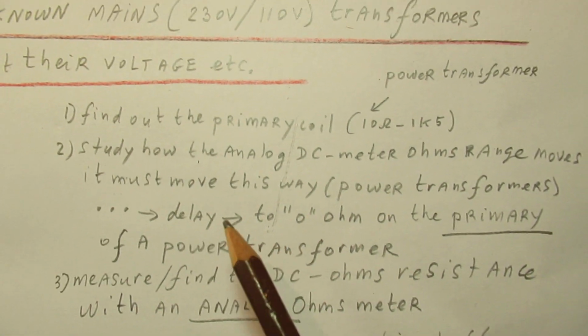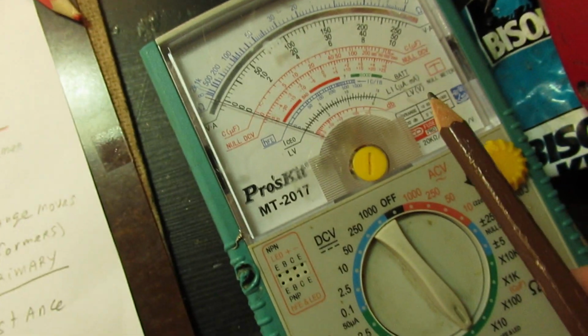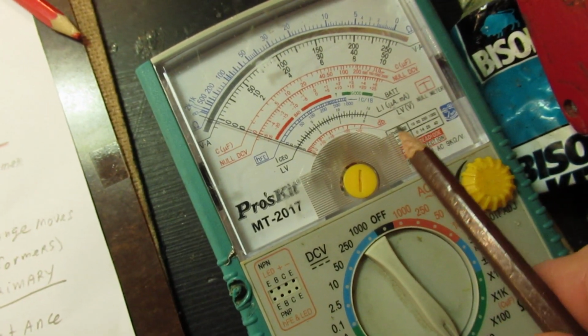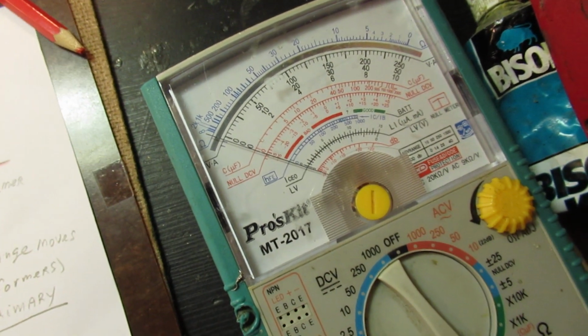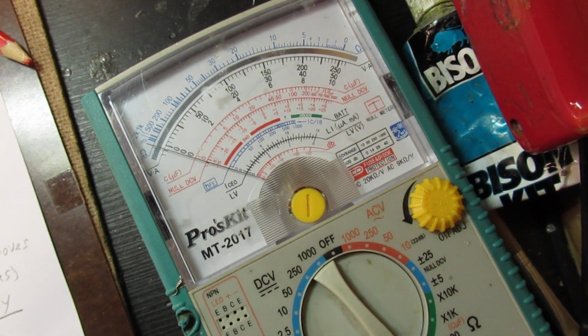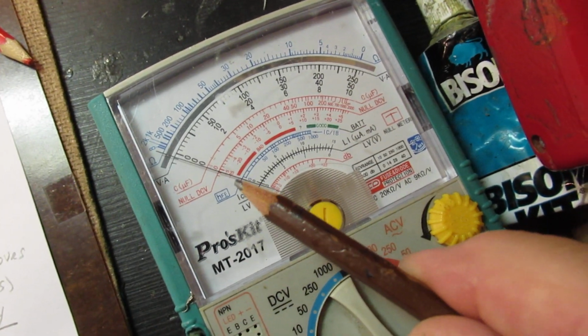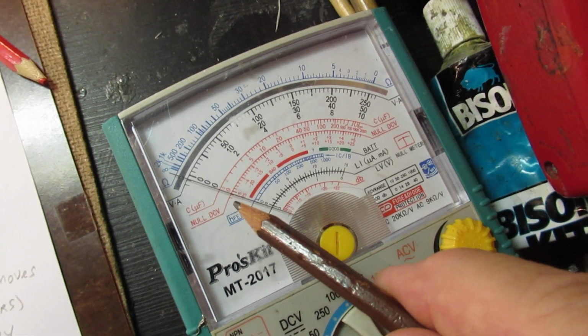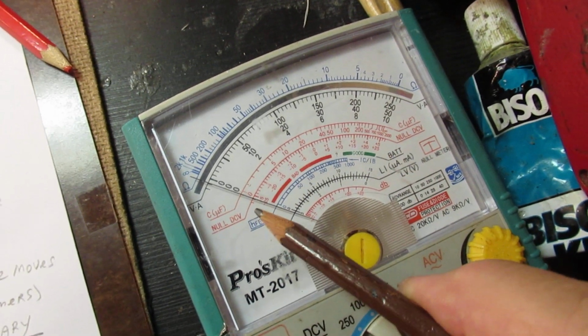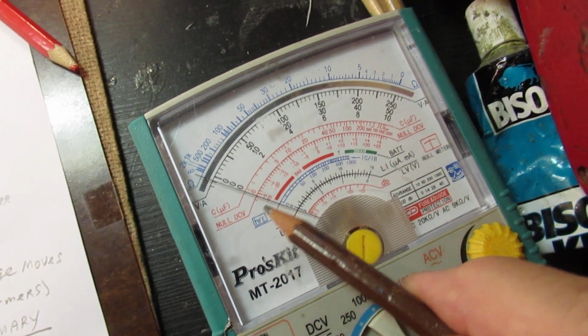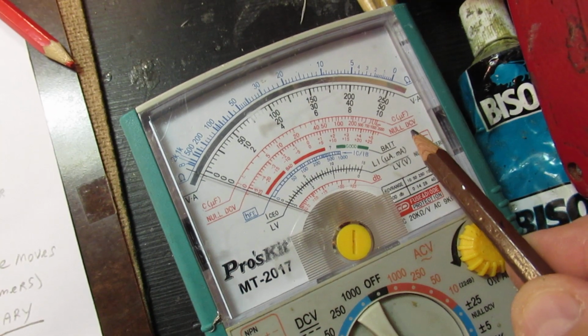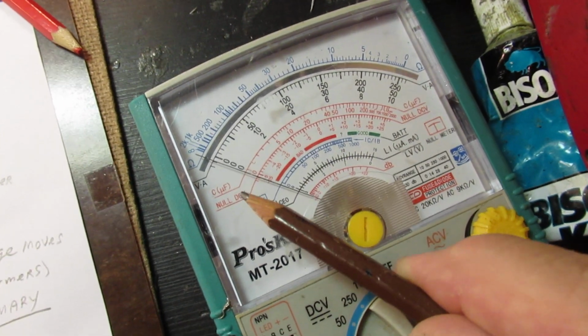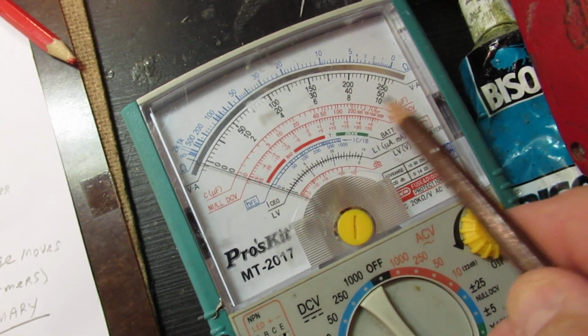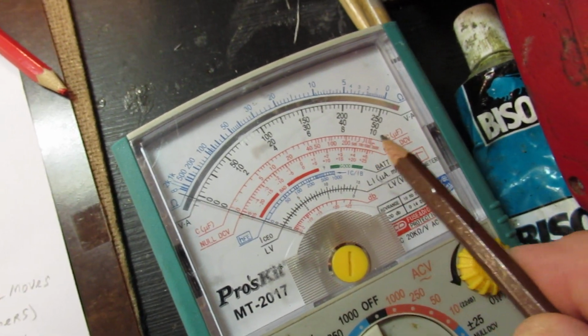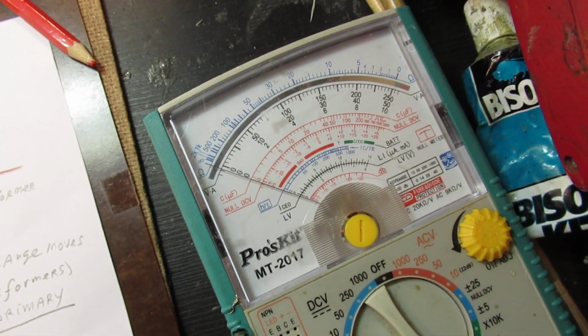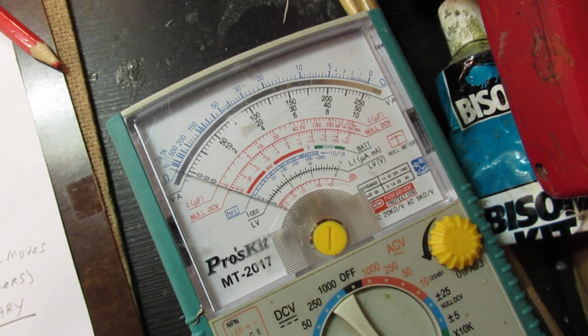For power transformers, when you connect a DC ohms meter to the primary, often in the 10 ohms up to 40 ohms range, you see the meter move, but not completely in a straight and direct way - it moves in a kind of delayed way. That has everything to do with the back EMF of the primary coil. So when you see this effect, slow here and quick here, you have an indication that you are on the primary coil.